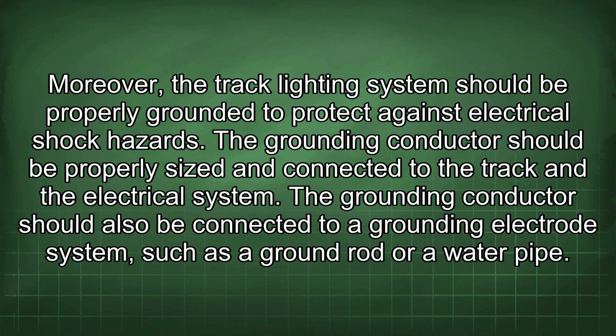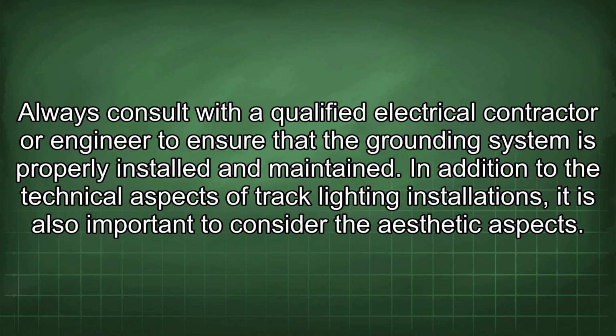Moreover, the track lighting system should be properly grounded to protect against electrical shock hazards. The grounding conductor should be properly sized and connected to the track and the electrical system. The grounding conductor should also be connected to a grounding electrode system, such as a ground rod or a water pipe. Always consult with a qualified electrical contractor or engineer to ensure that the grounding system is properly installed and maintained.